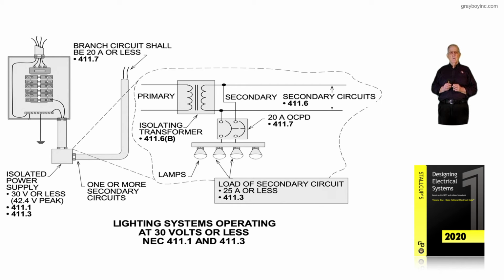The isolation transformer is discussed in more detail in 411.6(B), as illustrated in the illustration. So we have that isolation transformer, primary usually 120, and then the secondary coming off could have a 20 amp overcurrent device in accordance with 411.7 supplying the lamps that you see there. So for example, at the home I used to live in, Malibu lighting just plugged into a 120 volt outlet. You had your transformer, you just mounted it, and then you had your lights supplied by the secondary side, which wasn't harmful to anyone.